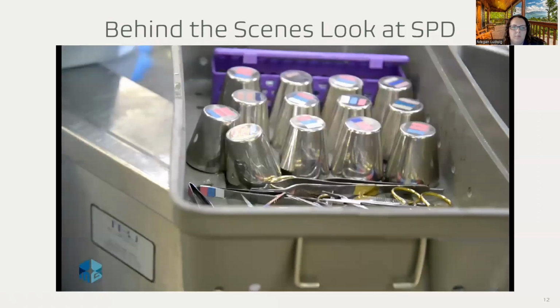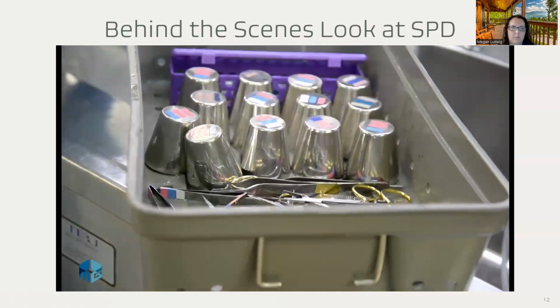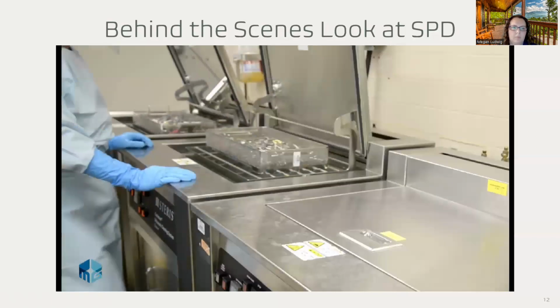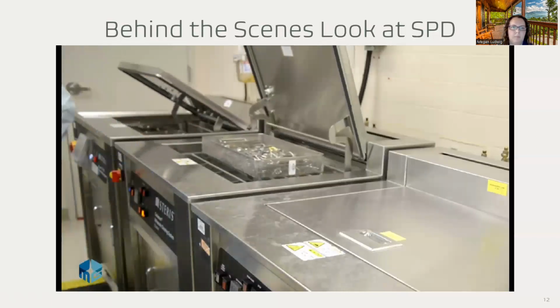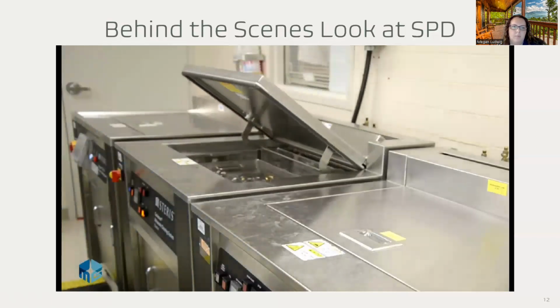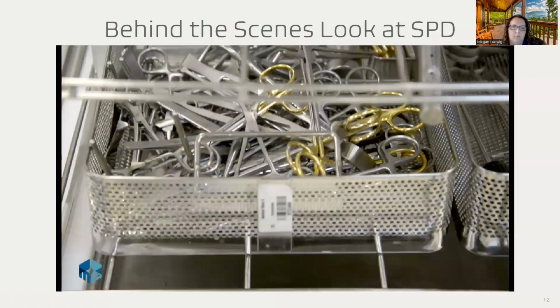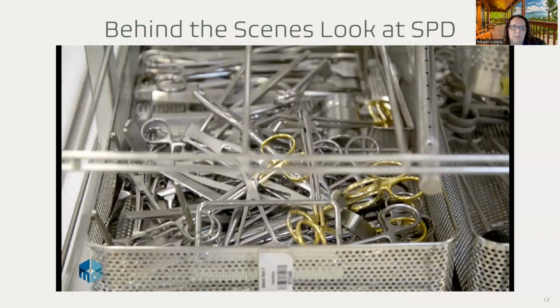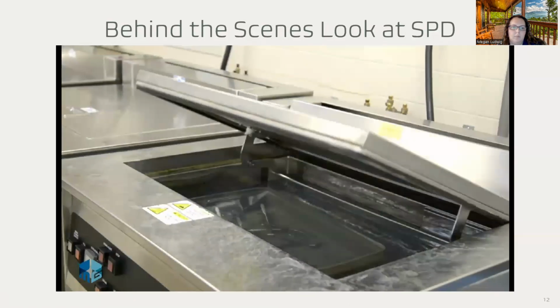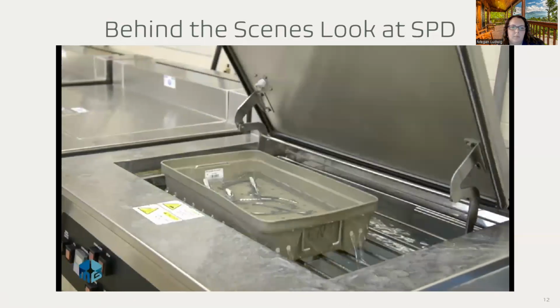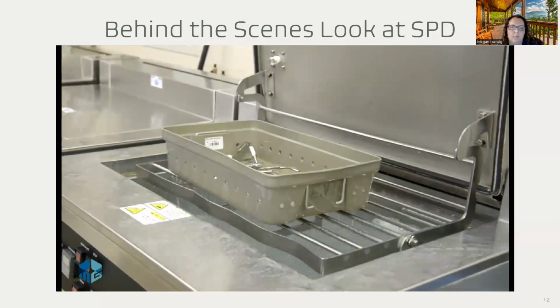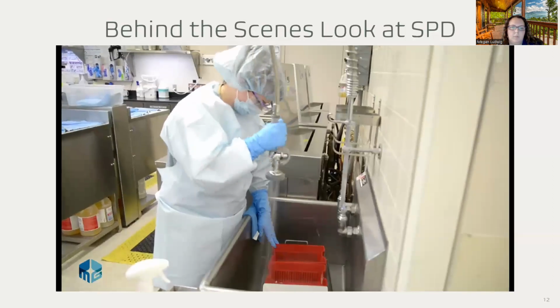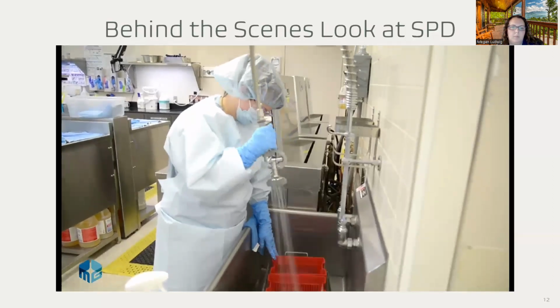With ultrasonic cleaning, we are removing the remaining biofilm that cannot be seen. Ultrasonic cleaning works by creating ultrasonic waves that travel through the water. These waves create tiny unstable bubbles, and when these bubbles come in contact with the instrument, they implode and remove the remaining biofilm. After all the biofilm has been removed, the instruments are rinsed and prepared for the final step of the decontamination process, mechanical cleaning.